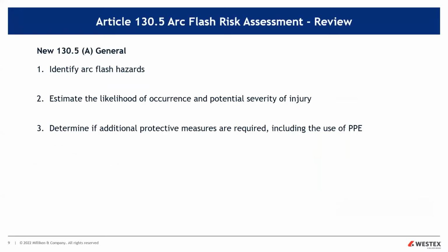Some review here. I know a lot of these folks here are experts on this, but you need to identify the arc flash hazards, and it may change if you've added or taken away certain equipment. So you need to identify those. And then of course, we need to estimate the likelihood of arc flash occurrence and the potential severity of injury, and then determine if additional protective measures are required, including the use of PPE. Now, the protective measures go all the way from the top of the hierarchy, elimination, down through engineering controls, administrative controls, and then PPE is the last line of defense.